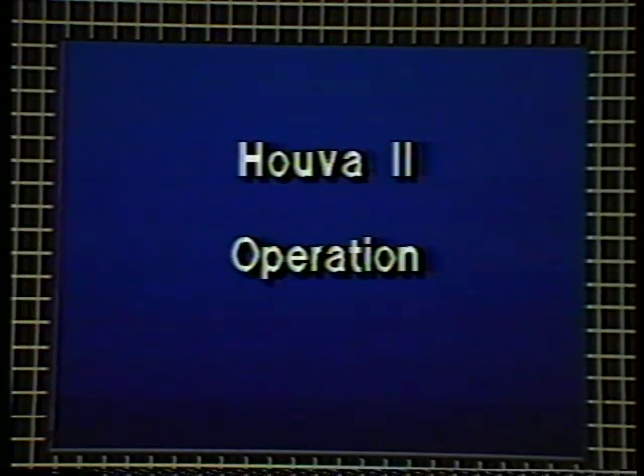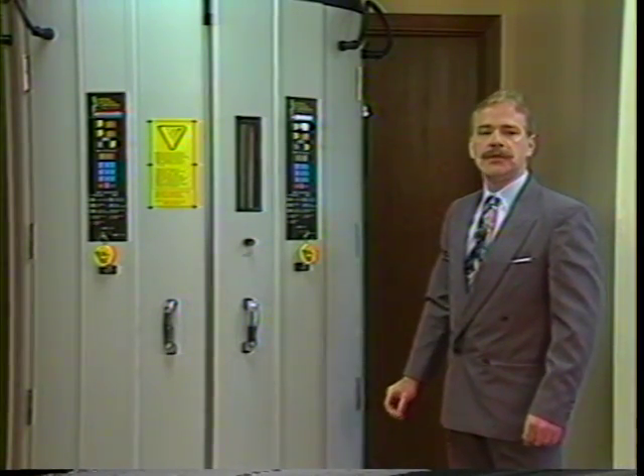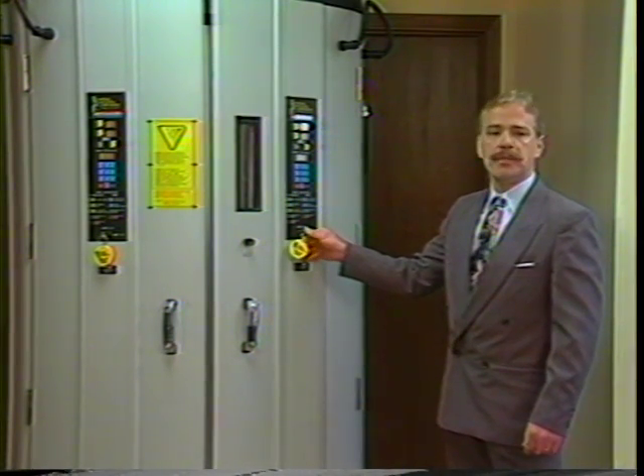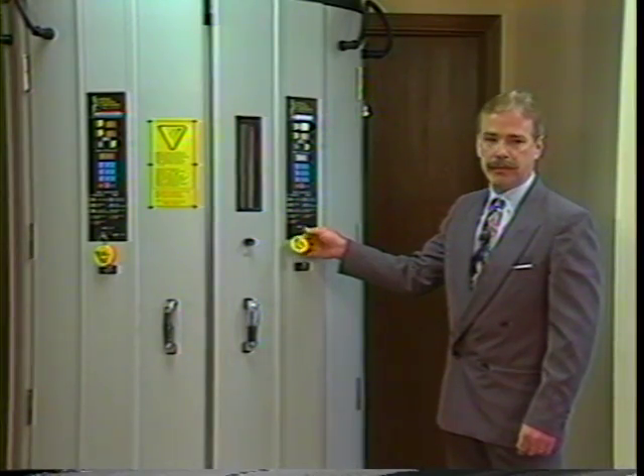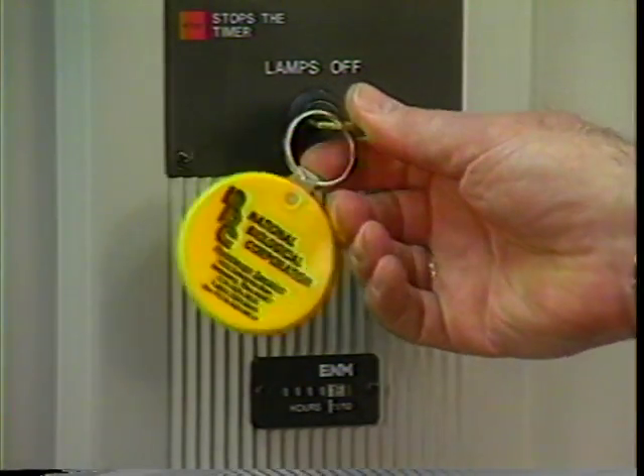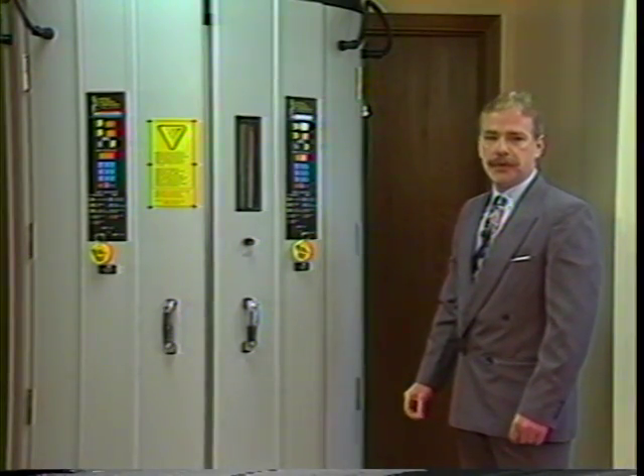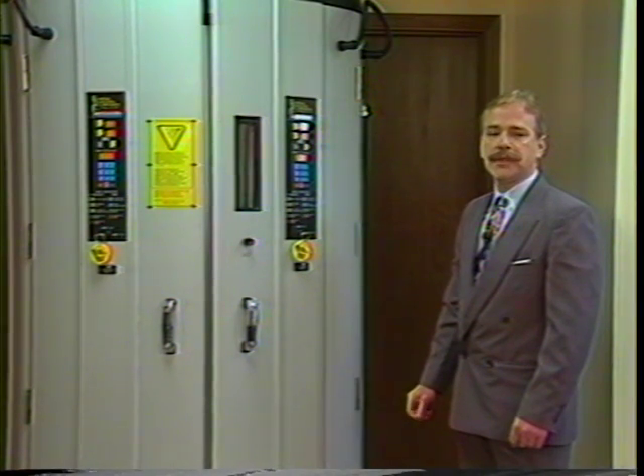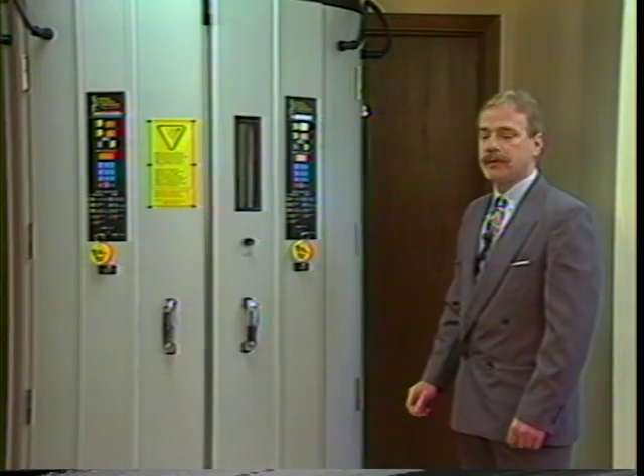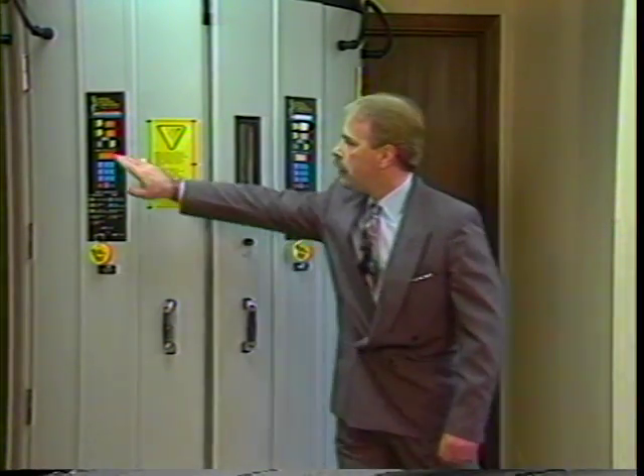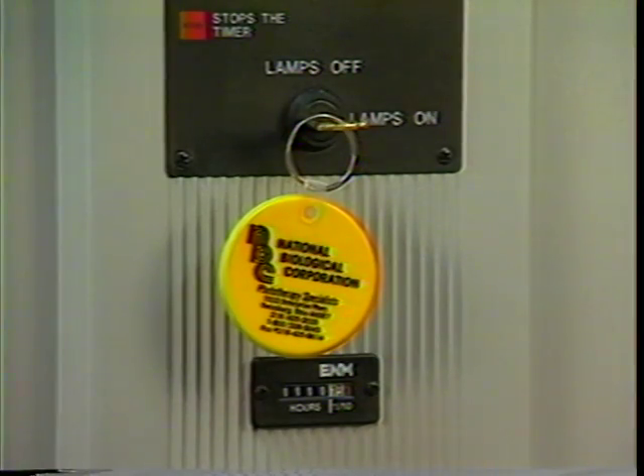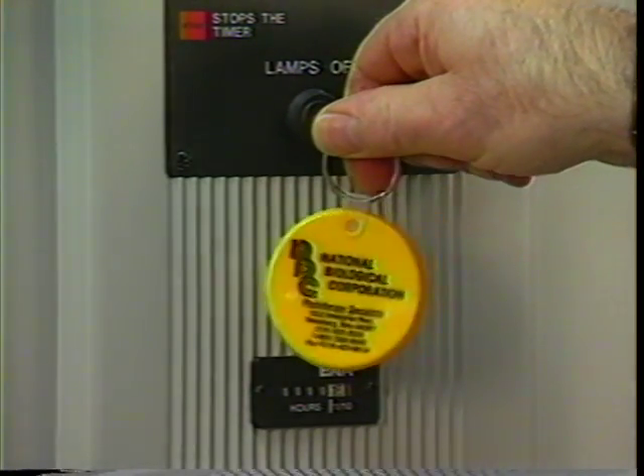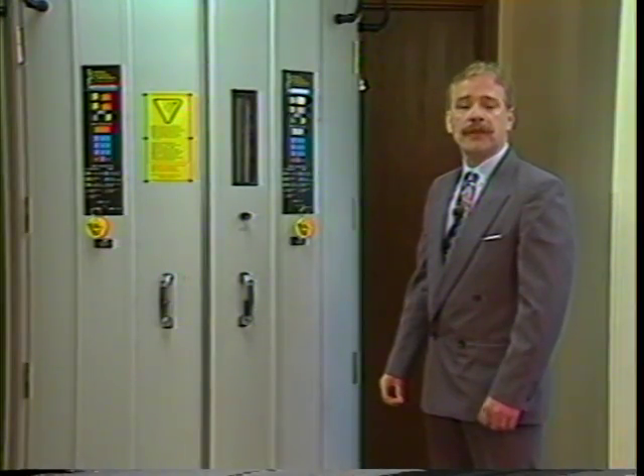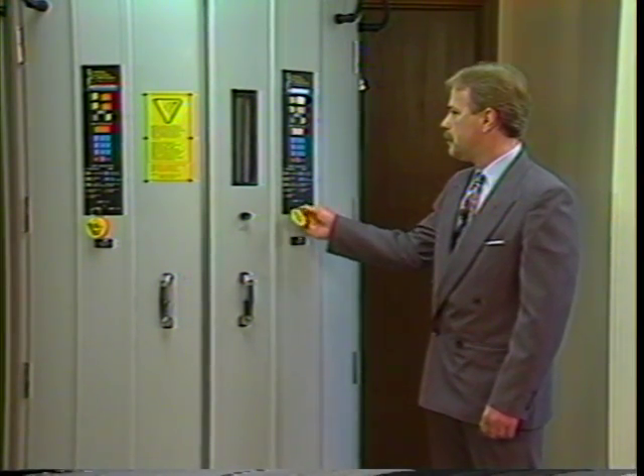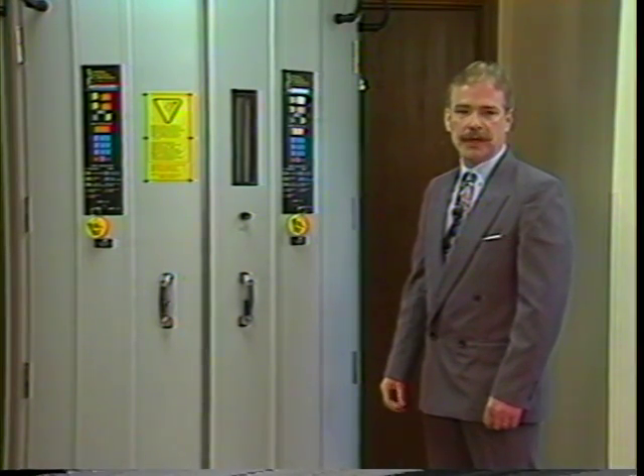To operate the HOUVA II system, first you must power up the unit by turning on both circuit breakers. At this time, you will turn the keys to the lamp's on position on either the UVA timer or the UVB timer, at which time you will hear a distinct single beep. Following the instructions in your user's manual, you will depress the yellow button marked mW/cm², and zeros will appear on the display window to the right side of the timer. If the key switch is turned to the lamp's off position, the device is disabled until the key is turned to the lamp's on position once again. This is a safety feature found only in the PhotoSense timer from National Biological Corporation.